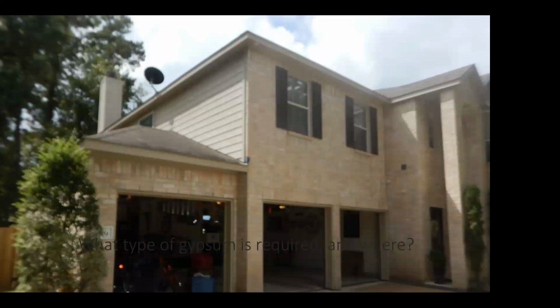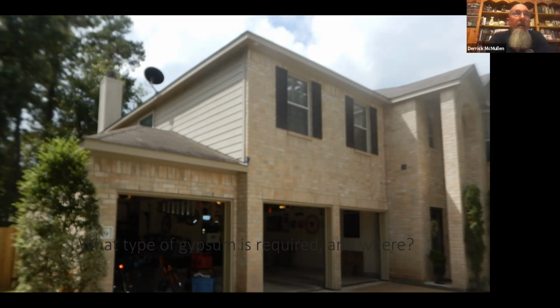Another one from when you were talking about the vents in the garage. In some houses, there is an air vent because a swamp cooler was installed to cool the garage. So there is a vent with grill and goes up to the swamp cooler. Is this permitted? If it penetrates that fire separation ceiling or fire separation wall, yes, it's a violation.